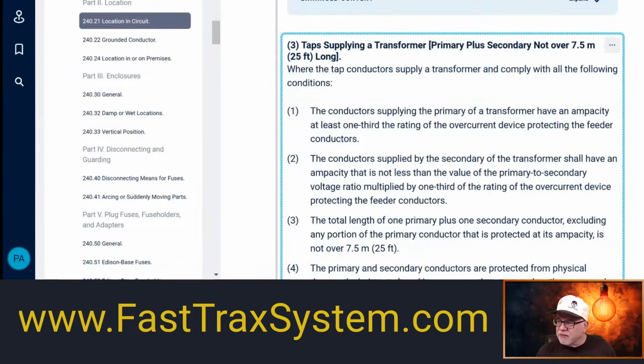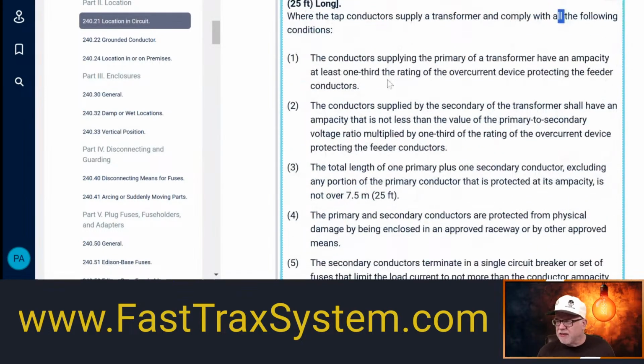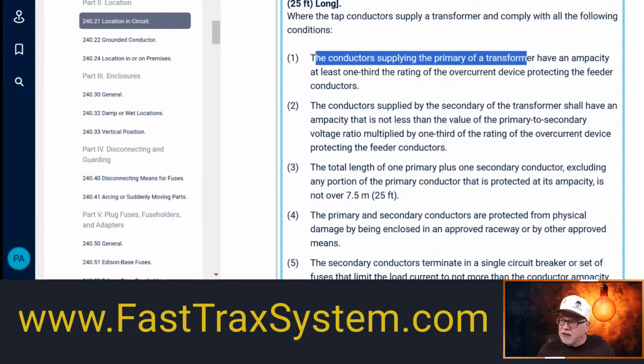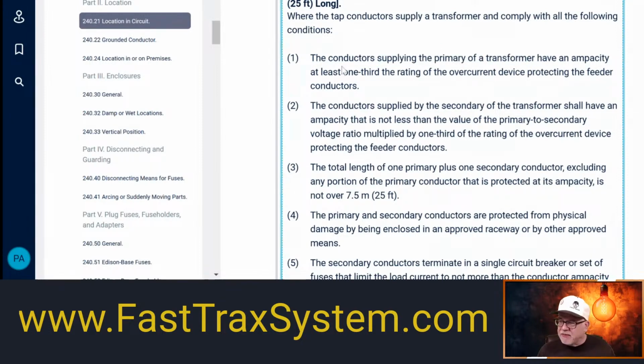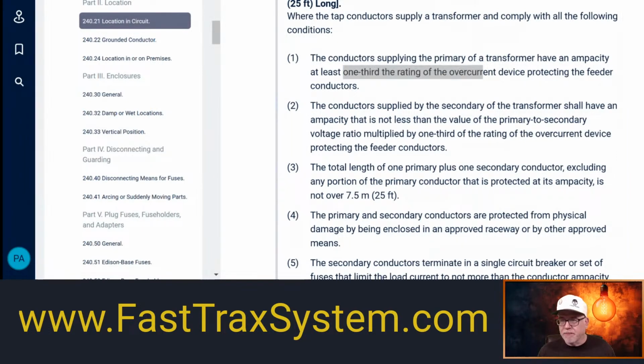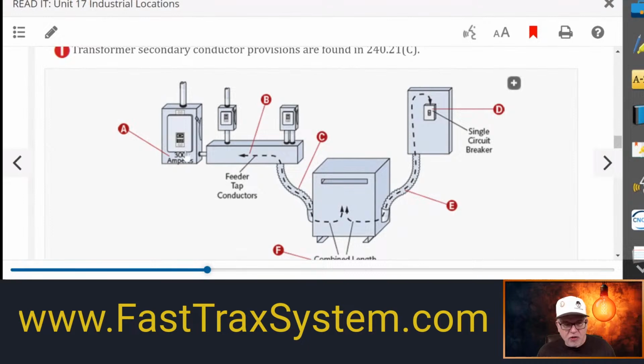It says where the tap conductors supply the transformer and comply with the following conditions. Okay. Now, all of these conditions, not some of them, not part of them, all of these conditions. It says, number one, the conductor supplying the primary of the transformer, they have to have an ampacity at least 1/3 the rating of the overcurrent protecting device for the feeder. Okay, well, let's take you back here.